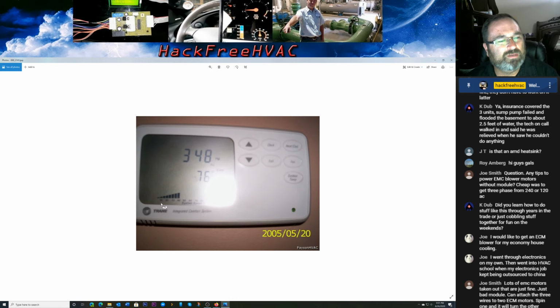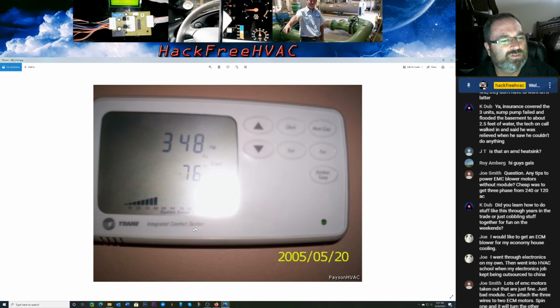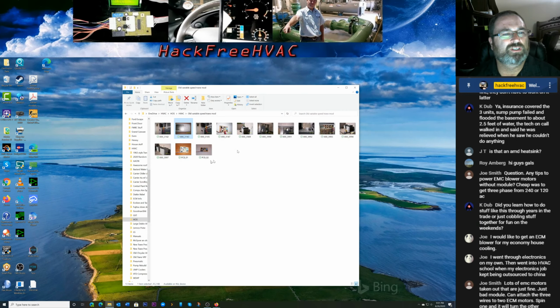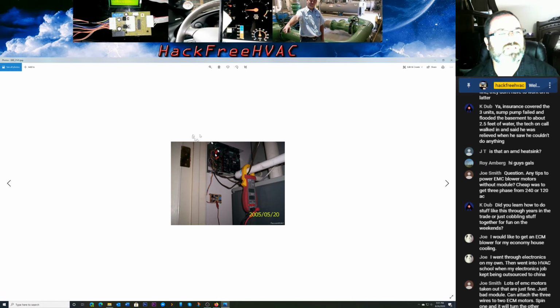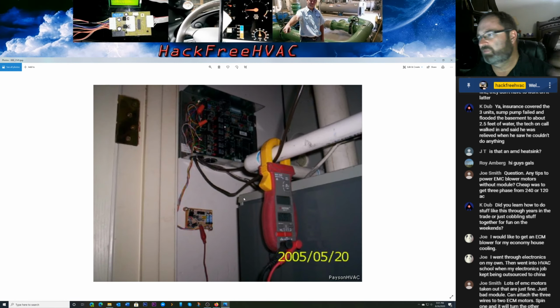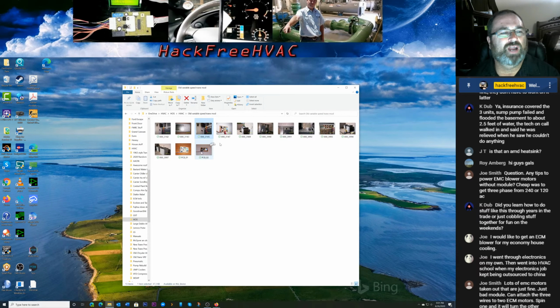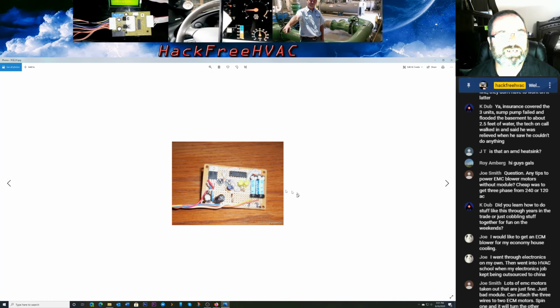Because the controller for the thermostat ramped up - see how it says percentage, and the bar graph went all up to right here, up and down. Integrated control system, comfort system, Trane, 100% variable speed. So it varied, and this interface board sent out the command to the furnace to run the speed of the blower, and then to the outdoor unit for it to run its speed. Well, they put that wrong air handler in there, which had your Y1 and Y2 in green. So what I did, I made this controller here.